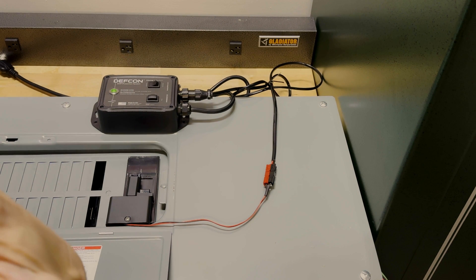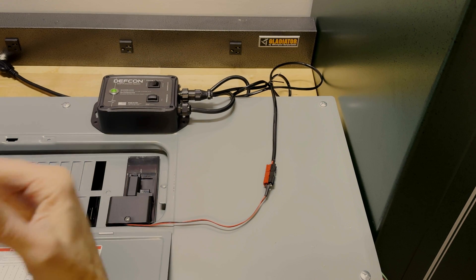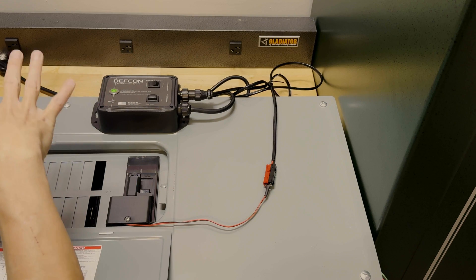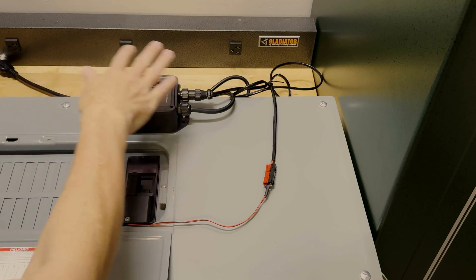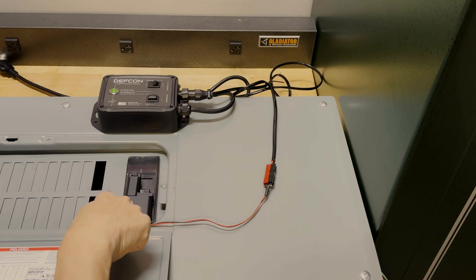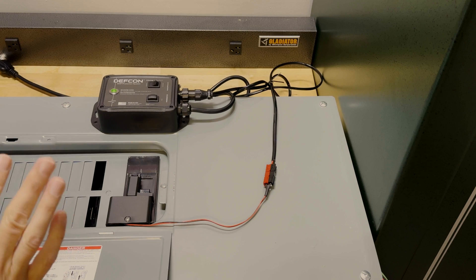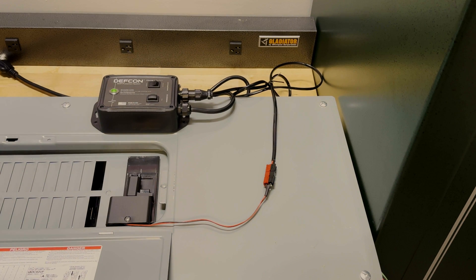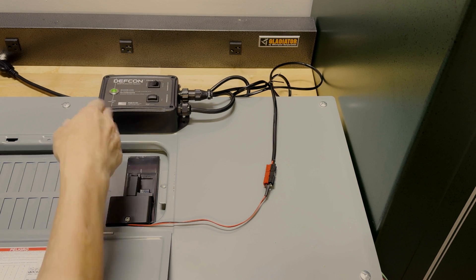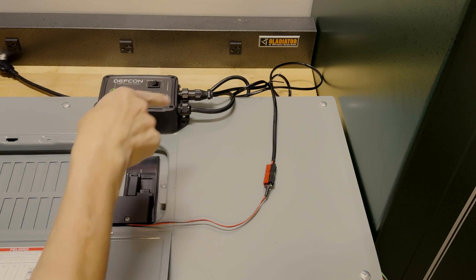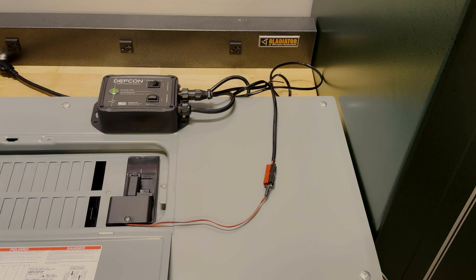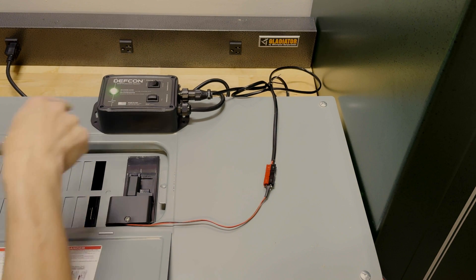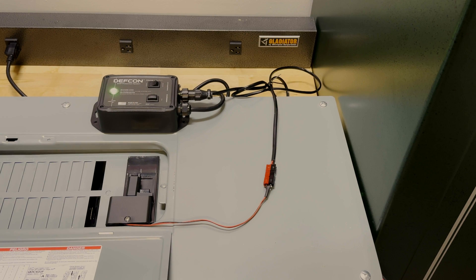Likewise, if you end up with an overvoltage condition, let's say due to a solar coronal mass ejection or the E3 of an EMP, as that voltage starts to rise on the power lines, this box will monitor those power lines and when they get too high, it will again drive the actuator assembly and trip the breaker, once again disconnecting you from the power lines, which is what you're trying to do, disconnect your home or business from that damaging energy source. So it detects both the E1-E2 radiated pulse as well as the overvoltage condition that will develop on the power lines. Either case will cause the breaker to trip. So I'll go ahead and plug it in. So now the unit is in this detection mode looking for the radiated pulse or the overvoltage condition.